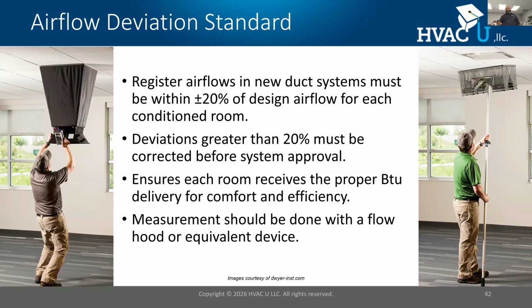Now, Brent brought this up earlier. He was talking about some of the different standards. Now, you got LEED, you got Energy Star, you got ResNet, you got ACA, you got BPI, you got all these standards. You have to use whatever your program is going to call for. We're a BPI training organization, so we often use BPI specifications. So this is what you see here on the screen. When working with registered airflows, we like to make sure that the duct systems are within 20%. Some programs are more aggressive. Some say 10%. So again, it depends on what program you're going to work with. The moral of the story: I have to have enough CFM coming out the registers to deliver the BTUs to offset what I'm doing, either heating or cooling. So whatever program you're going to work on, make sure you understand those numbers or targets.